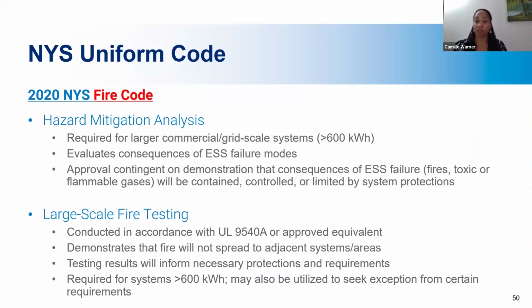Jumping into the fire code, there's a few things I'd like to highlight. As a part of New York State Uniform Code, Chapter 12, hazard mitigation analysis is required. This asks if the system fails, what systems are in place to contain, control, or limit that failure. Chapter 12 also requires large-scale fire testing, so UL 9540A or an approved equivalent, to make sure that fire will not spread into adjacent systems or areas, and it also informs necessary protections and any requirements that system needs. Again, it's a data collection test, not a certification.